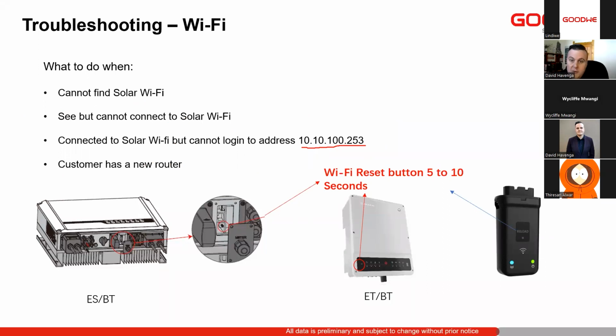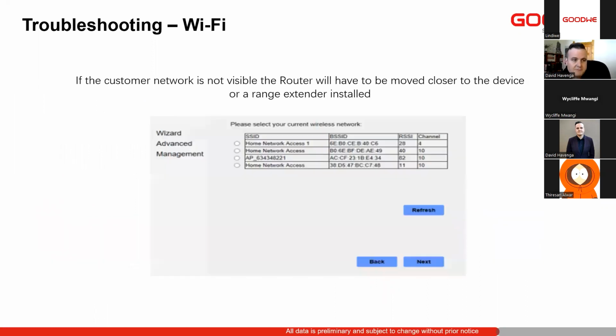So this is also applicable. If the customer's changed networks or he has a new router or anything like this, then we need to reset the Wi-Fi module. So we can press and hold the reset button. It will be in different places on different devices, and all the new Wi-Fi modules have it on the Wi-Fi module directly. You can press and hold that for 5 to 10 seconds, and that will fully reset it and clear the previous Wi-Fi settings.